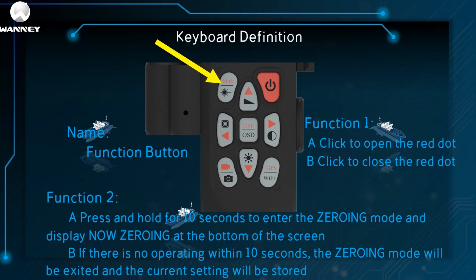This is the function button. The first function is to switch the red dot, just click it. The second function, press and hold for 10 seconds to enter the zeroing mode, and 'zeroing' will display at the bottom of the screen. If there is no operation within 10 seconds, the zeroing mode will be exited and the current setting will be stored.